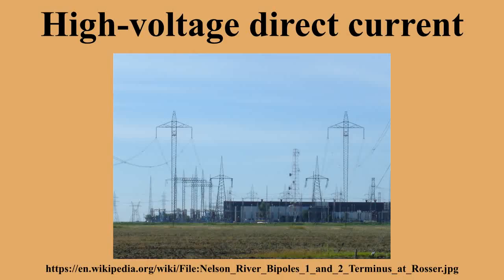High-voltage transmission. High voltage is used for electric power transmission to reduce the energy lost in the resistance of the wires. For a given quantity of power transmitted, doubling the voltage will deliver the same power at only half the current, since the power lost as heat in the wires is proportional to the square of the current for a given conductor size, but does not depend on the voltage. Doubling the voltage reduces the line losses per unit of electrical power delivered by a factor of 4. While power lost in transmission can also be reduced by increasing the conductor size, larger conductors are heavier and more expensive.